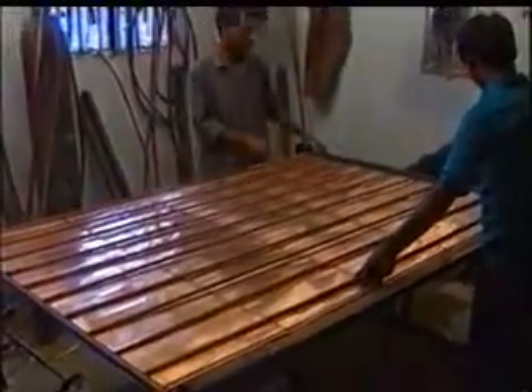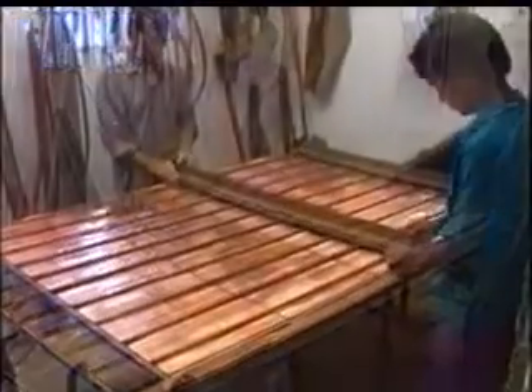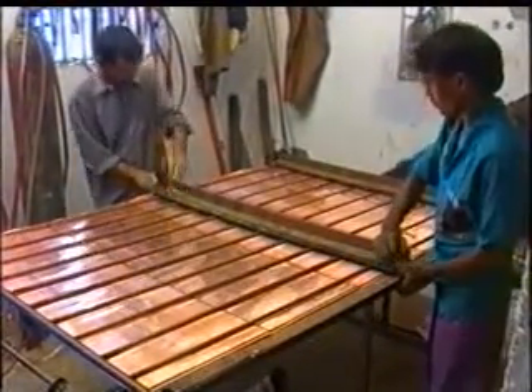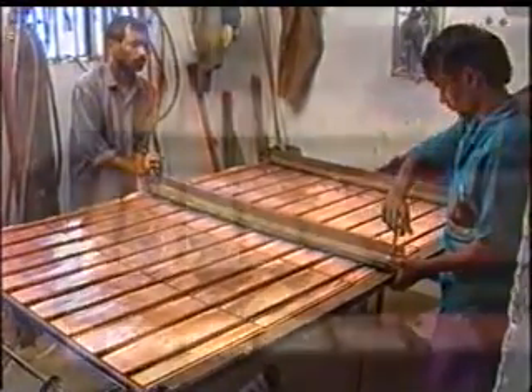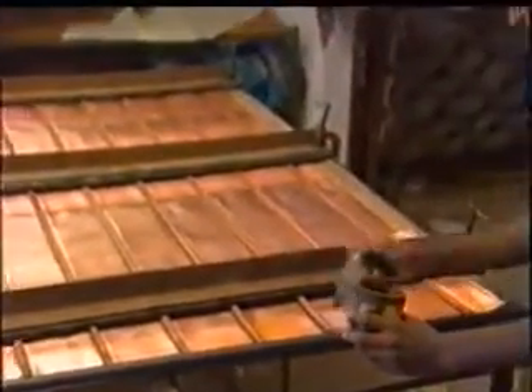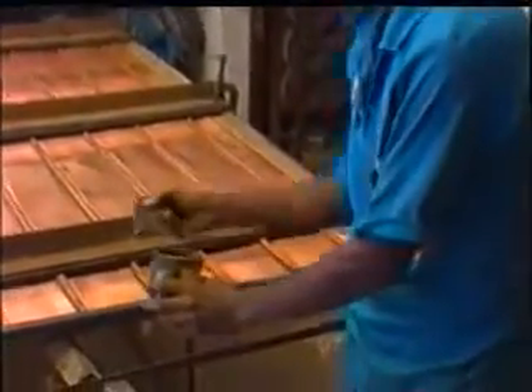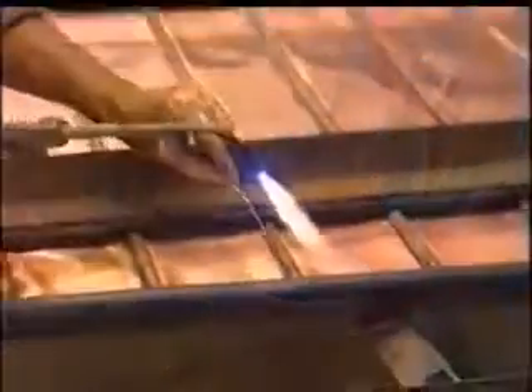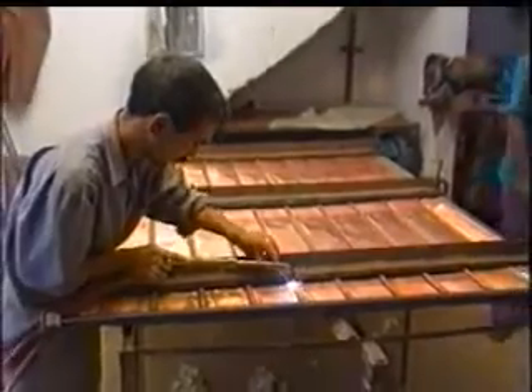Then the riser tubes and the main tubes assembly is pasted on the grooves of the sheet and clamped for tightening it. The riser tubes and the absorber are soldered for a good thermal and mechanical contact. Thereby, the riser tubes are firmly attached to the absorber sheet. The absorber sheet is coated with black coating such as black chrome so as to absorb most of the solar radiation falling on it for heating the water.